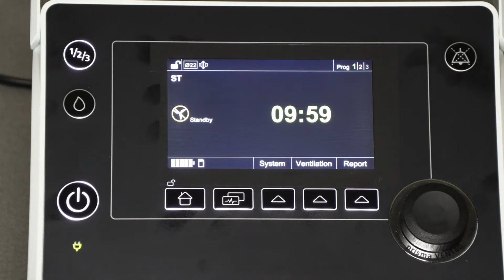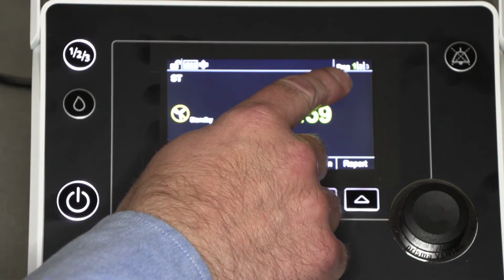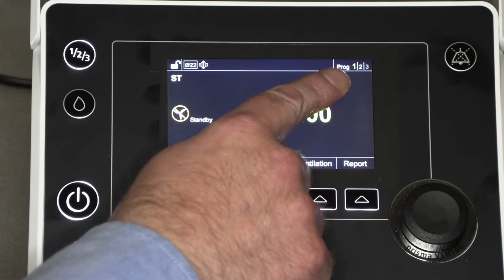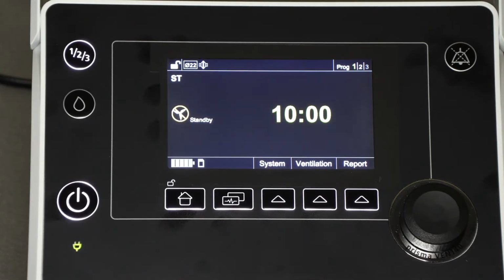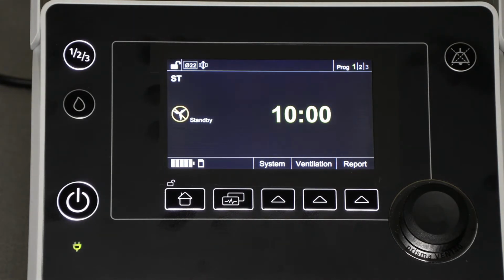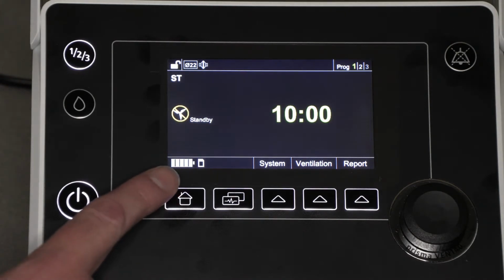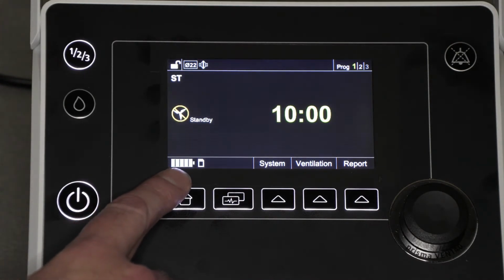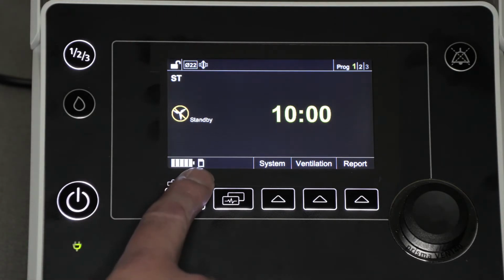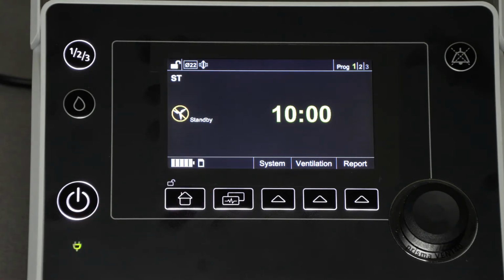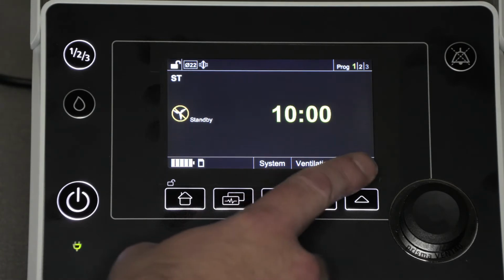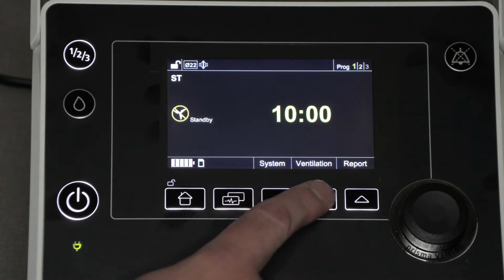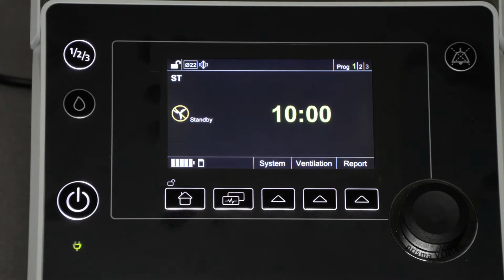On the top right, you'll see information relating to the ventilation programs. With the number 1 being larger than the other numbers, this is showing that of the 3 ventilation programs available, the settings in program 1 are what will be used when therapy is started. On the bottom left-hand corner, you'll see the battery symbol. If this is flashing, it means that the battery is currently charging. Beside that, you'll see the SD card symbol, showing that an SD card has been inserted and is present in the device. Accessing the system, ventilation or reports menus can be done by pressing the function button under the name of the menu you want to access.